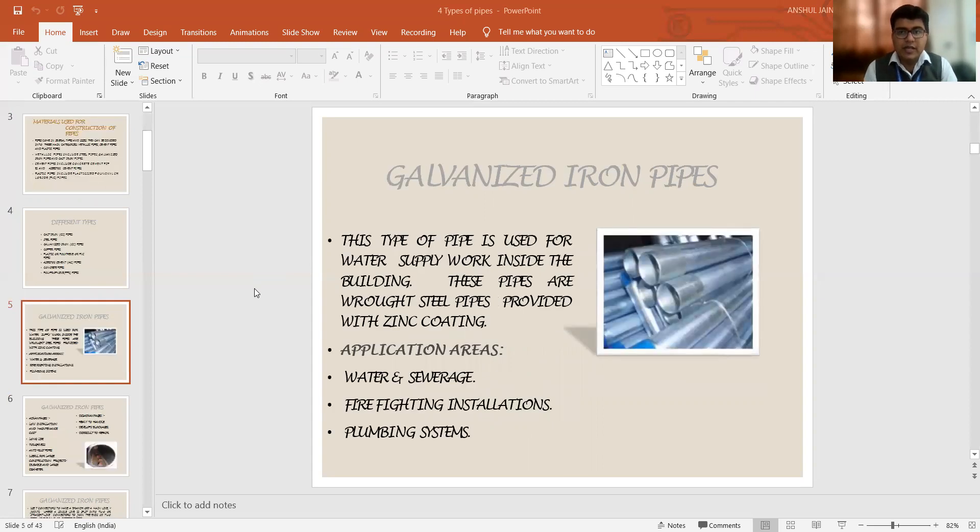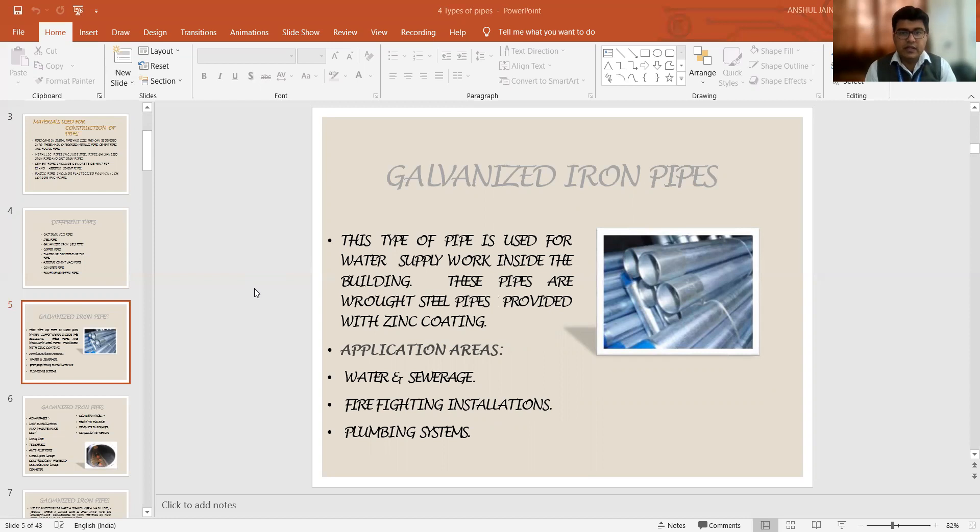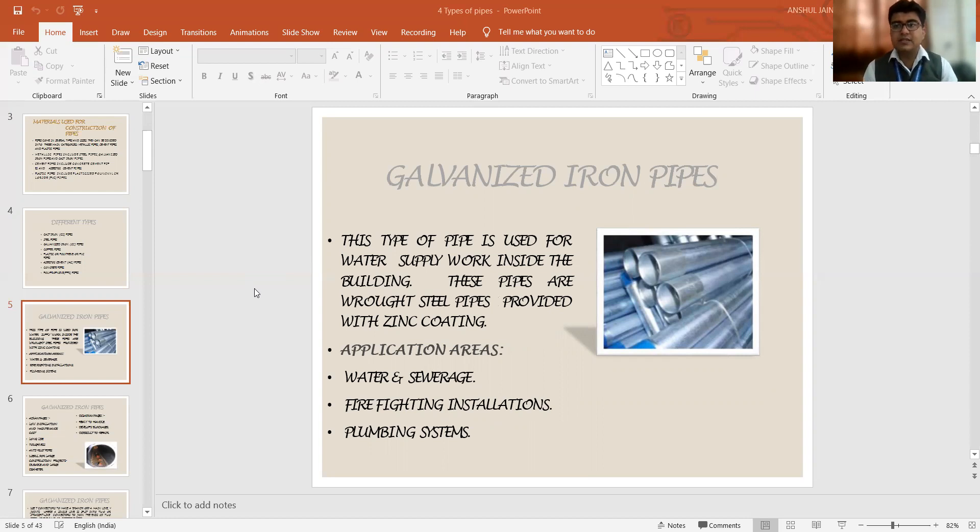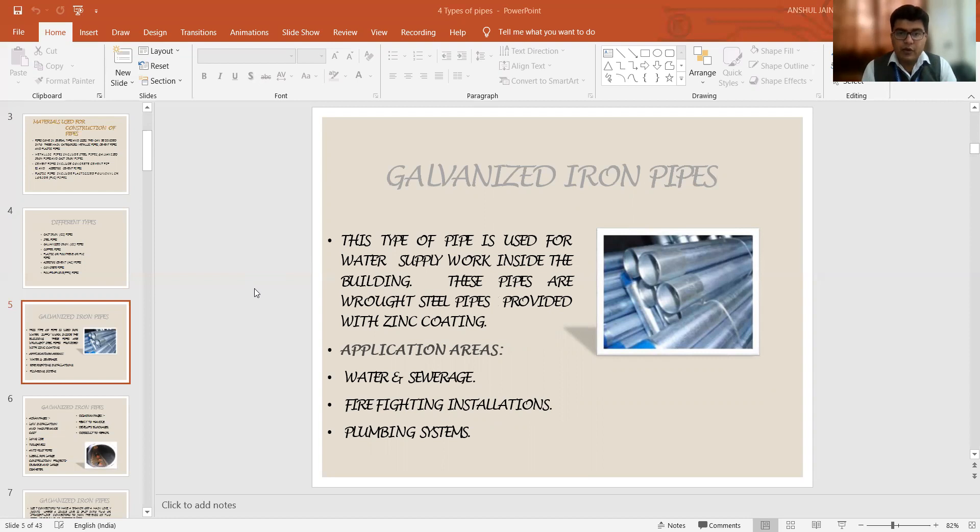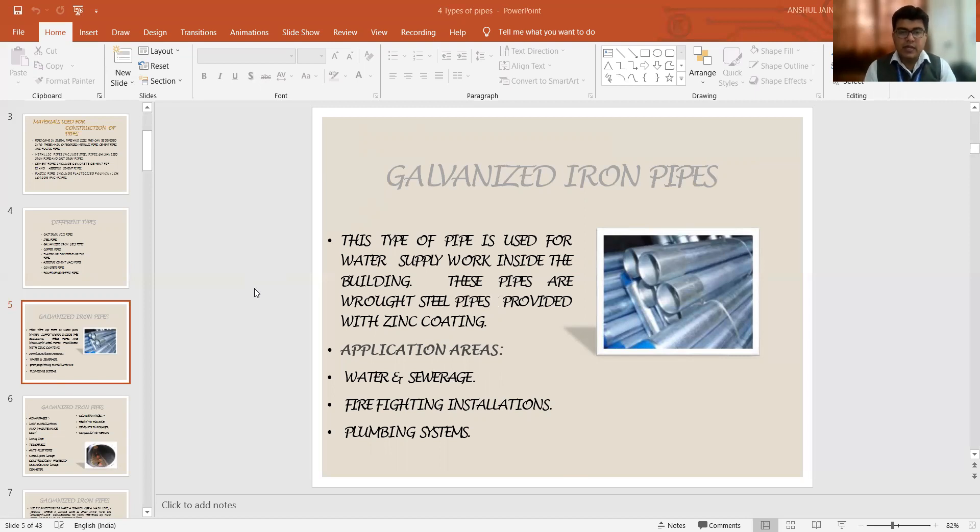So if we talk about the galvanized iron pipes, this pipe is utilized for water supply work inside the buildings and specifically these pipes are made up of wrought steel. They are provided with a zinc coating so that the resistance against weathering can be provided. The application areas are: we can use it for water supply and sewerage systems, firefighting installations because they can bear good pressure, and we are utilizing them for plumbing systems.